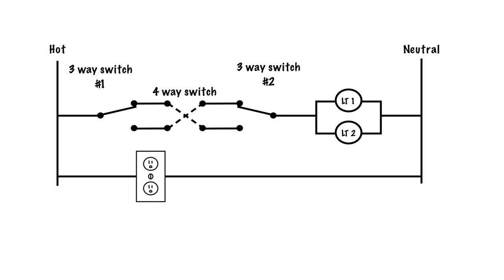Throwing in a four-way switch means you're going in between the two three-way switches. Four-way switches only have traveler terminals — no common terminals. If I wanted to switch from more than three locations I would just throw another four-way switch in. So a schematic will always have three-way switches on each end, and if you want to switch from more than two locations you just add four-way switches in between.